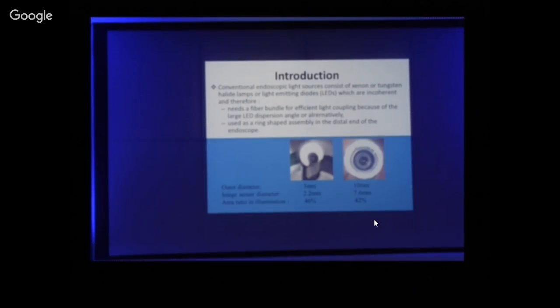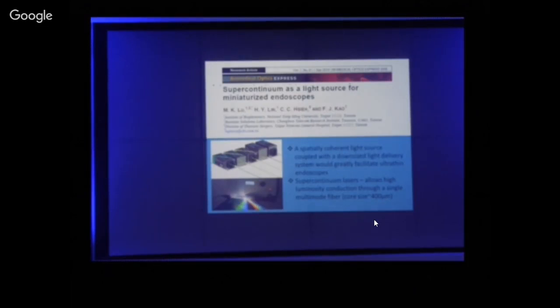Another alternative is to use a ring-shaped LED assembly at the distal end of the endoscope, and also use the CMOS sensor there. But in that case, the need for circuitry to operate those LEDs and CMOS sensors will again increase the diameter of these endoscopes. Now, if we can use spatially coherent light sources, which means lasers, a downsized light delivery system will help us reduce the diameter a bit. But for endoscopy, we need white light sources.